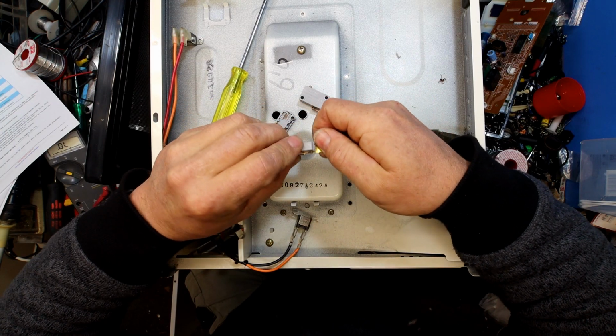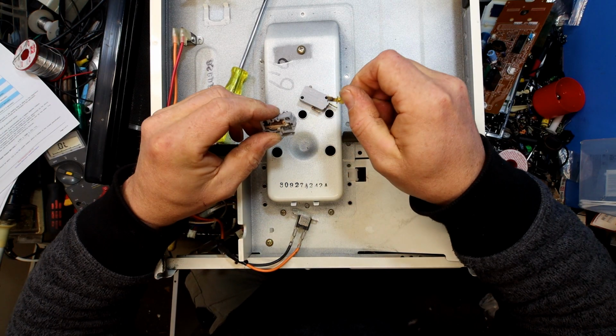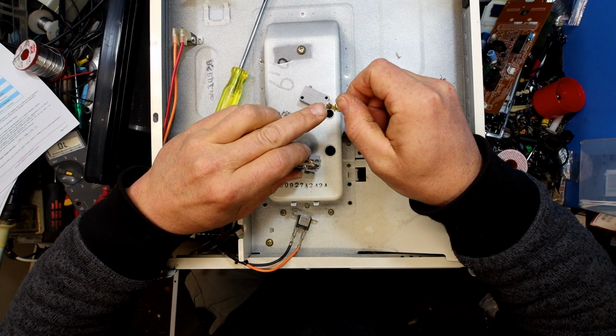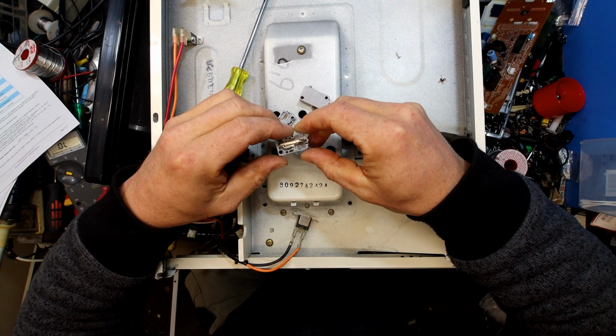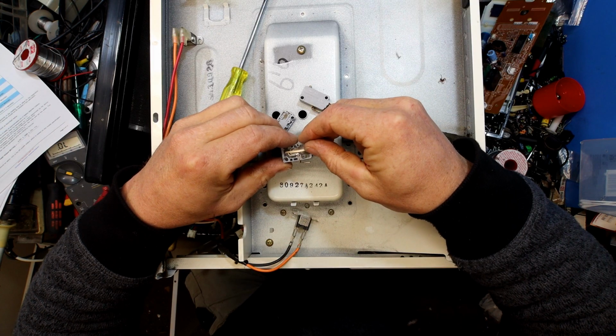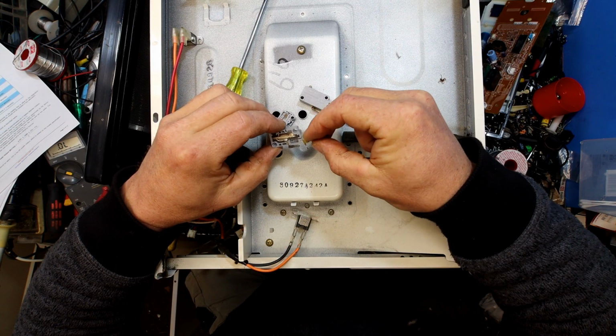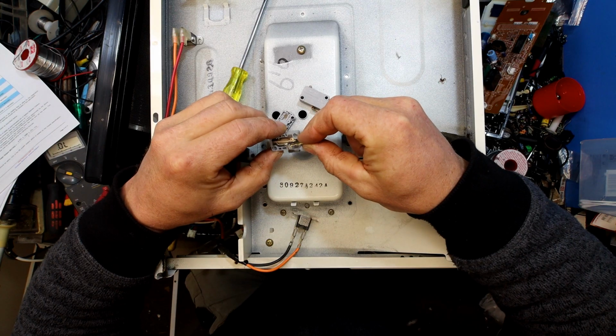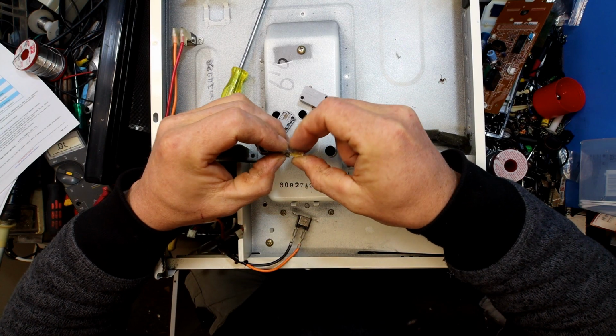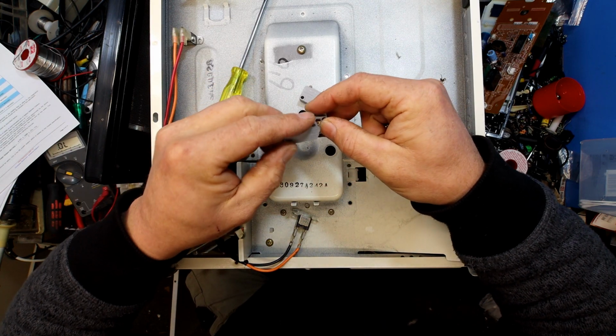Yeah, that one's pretty blackened. The main bit's not too bad, but you can see it's been arcing around there. You can take this other piece out as well. Can be cleaned up, but usually better if they've been causing trouble to replace them, but always worth an inspection.